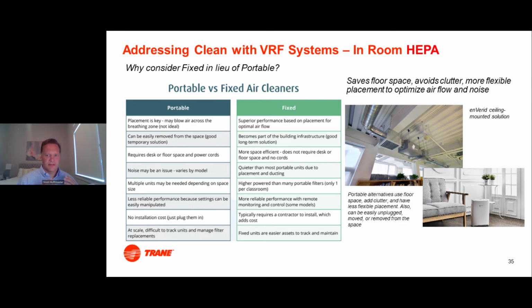And why would you do this? Certainly that's going to cost more than a portable, but that also means you're not going to be giving up floor space. You're going to make sure you've got something that's going to be working. You're going to make sure that it's on when your building's occupied, off when your building's not, or at least on a night setback. You can ensure your sound ratings are correct. That is a big challenge for in-room air filtration, is sound compromises that we are challenged with. So all of these different things are reasons that for Trane, we're traditionally recommending a fixed HEPA if possible.